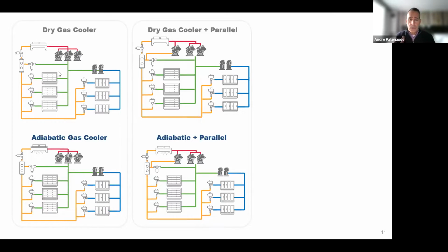However, we wanted to look at the middle of the page here, which is parallel compressor or intermediate stage compressor. You can see that of those 3 compressors at the top, one is separated from the main medium temp suction group, and you've got a yellow line going to it. And that yellow line is also connected to the flash tank. And the beauty of parallel compression is that its suction pressure is approximately, give or take, 100 PSI higher than medium temp suction because it's coming from the flash tank. That means your gas is denser and your compression ratios are much lower on the intermediate stage compressor. So you can do that.